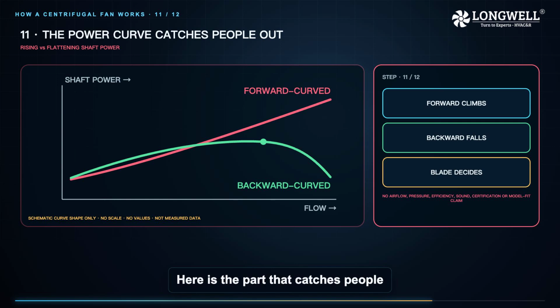Here is the part that catches people out. Because a backward curved wheel throws less velocity at a given tip speed, its shaft power flattens and then falls away as flow increases, instead of climbing. A forward curved wheel keeps demanding more power the more air it moves, which is why an oversized duct or a missing filter can pull its motor into overload. Blade shape decides that behavior, not the label on the motor.